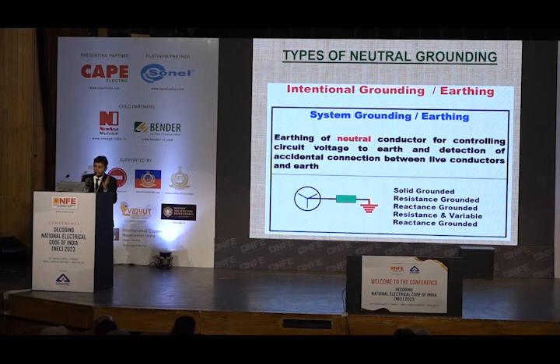Now, time to talk about system earthing. We have these five common types of system earthing in our systems: solid grounded system, which is called effectively grounded system, resistance grounded, reactance grounded, and variable reactance grounded.